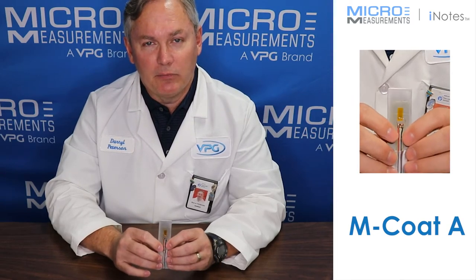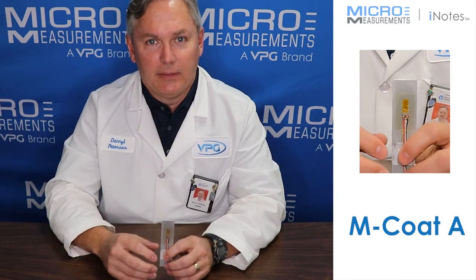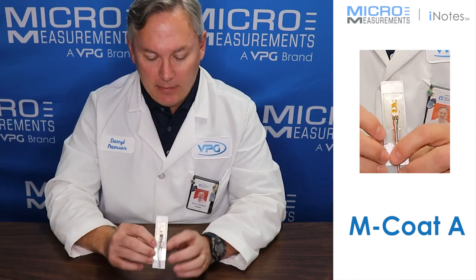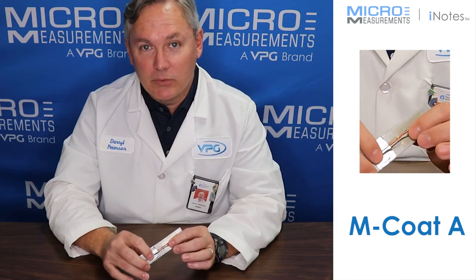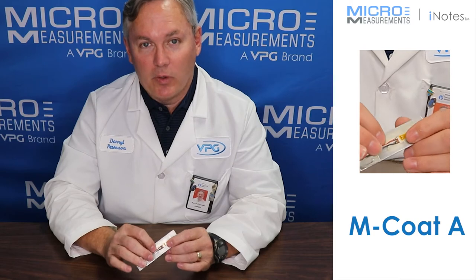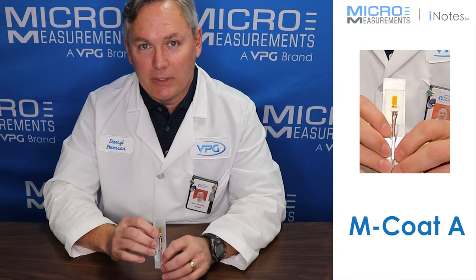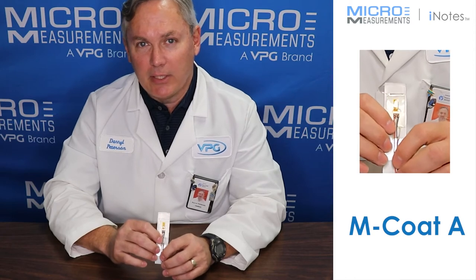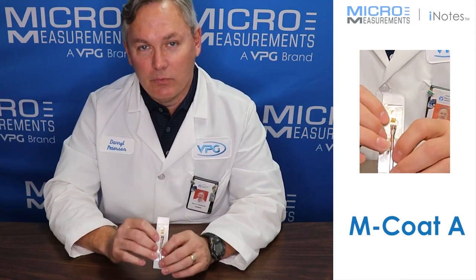Some applications where maybe you've got a dynamic or a vibratory type measurement in a laboratory setting, you might consider using M-Coat A. It's our most common environmental coating for strain gauges, really intended to be used in the laboratory, not so much out in the field, because moisture given enough time will go through the M-Coat A.